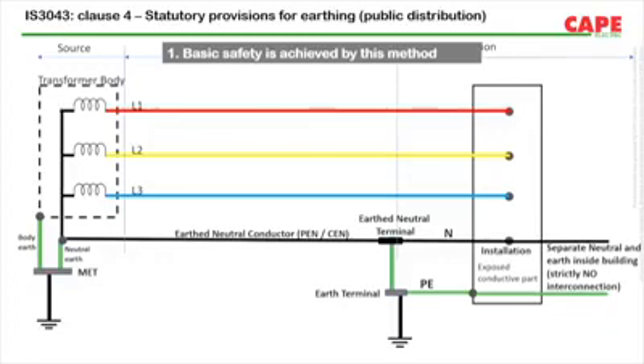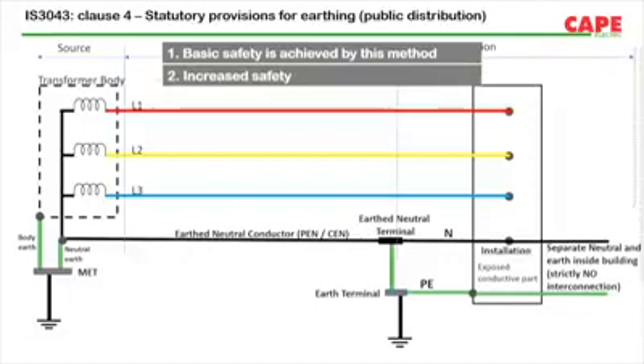The earth terminal in the incoming DB of the installation can be used to reduce touch voltage in the building. All extraneous conductive parts in the installation shall be connected to the earth terminal in the incoming DB. This earth terminal also can be connected to an earth electrode in soil. This is an additional safety measure. This extra safety measure improves the safety in the installation because it reduces the fault voltages or touch voltages.